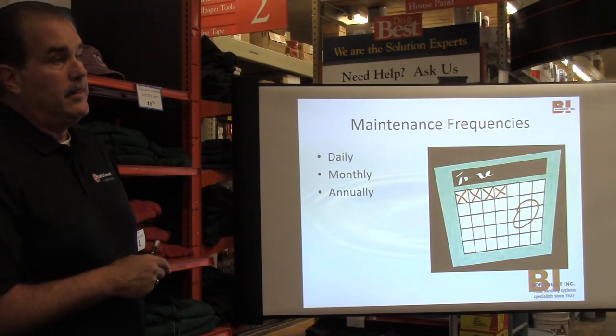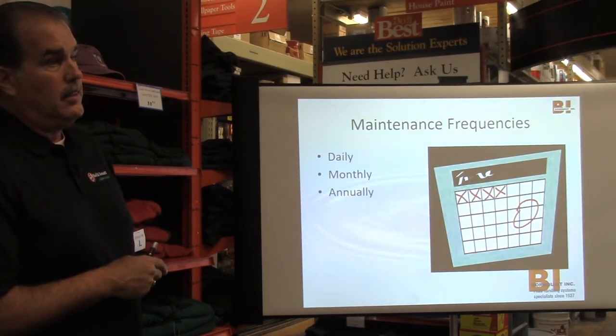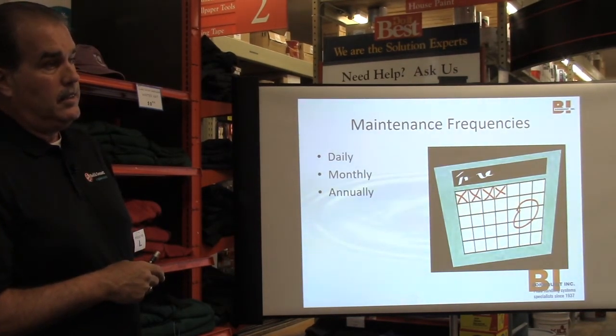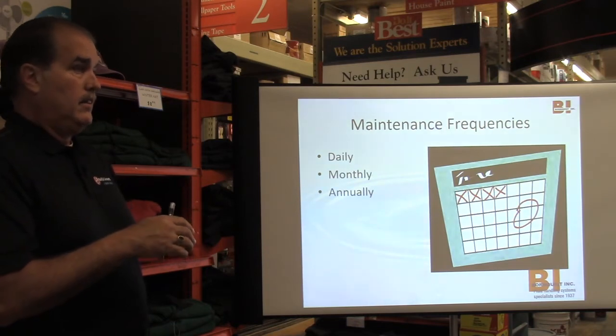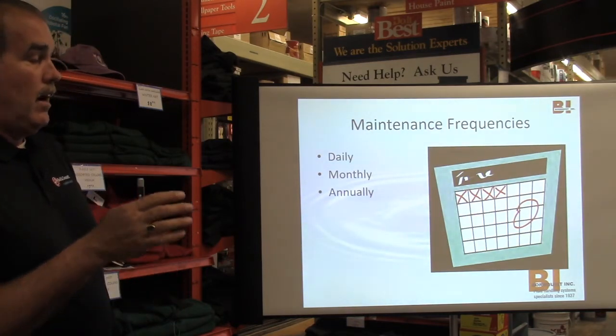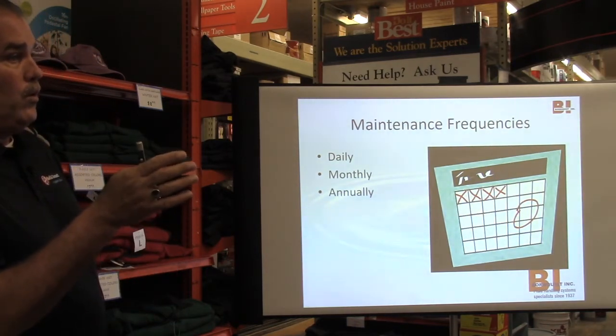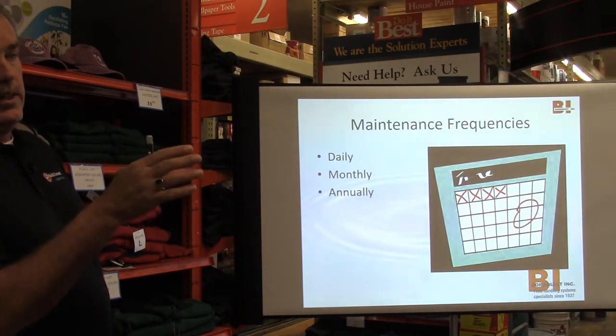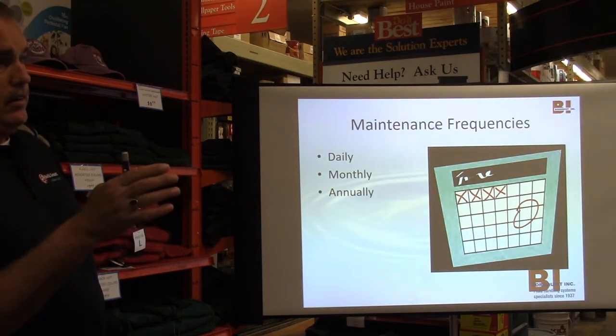Yes, sir. I was always told that it was good once a week to go in and just hit the flush valve for a minute, and it's usually pretty nasty water that comes out. But you're saying not changing the water, so now I'm wondering. No, you're talking steam. I was talking hot water. Oh, that was hot water, not steam.